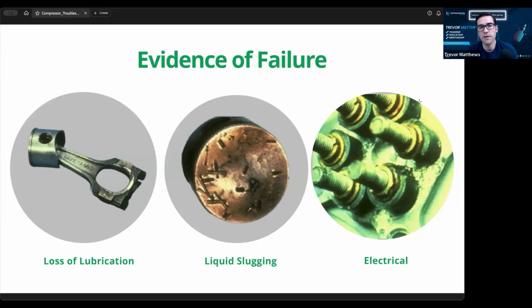Yeah, and it's important to do this. In all my compressor courses and training courses, I get them to go out and actually apply that stuff, because everything's based on facts. Refrigeration's facts. There are no real hypotheticals. You get the numbers, and this is what's happening. You get the pressures, you get the temperatures, you check the coils, it's visual, you're touching stuff, you're listening to stuff, you're getting your volts, your amps.